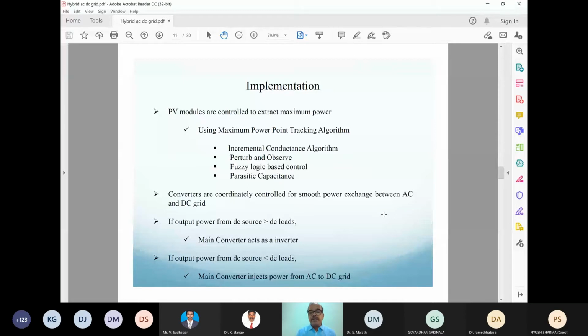If output power from the DC source is greater than the DC load, the main converter acts as an inverter. If output power from the DC source is less than the DC load, the main converter injects power from AC to DC, acting as a converter. So the main converter can act as either inverter or converter, as explained here.